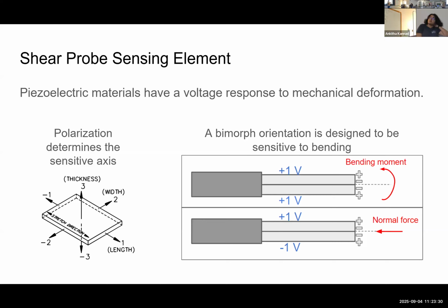The way the shear probe works is that it's 3-1 polarized. So you measure the voltage across the three face, and you want to be sensing a deformation in the one axis. So it's configured in this way that's called a bimorph, which is sensitive to bending, but insensitive to a normal force. So the shear probe actually has two piezoelectric plates that are oppositely aligned. So if you just take one of those, if you just look at the top one and you stretch it and you measure across the top and the bottom, the stretching of this will give you a voltage response.